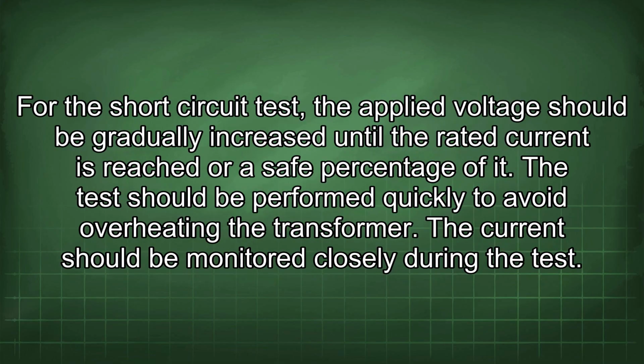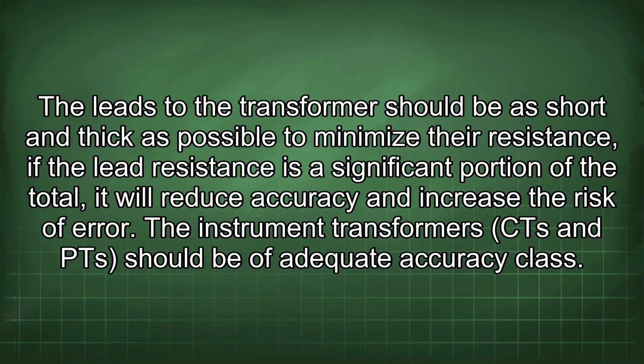For this short-circuit test, the applied voltage should be gradually increased until the rated current is reached or a safe percentage of it. The test should be performed quickly to avoid overheating the transformer. The current should be monitored closely during the test. The leads to the transformer should be as short and thick as possible to minimize the resistance.